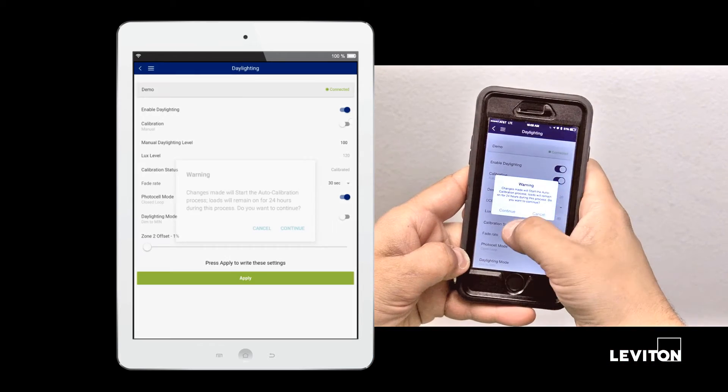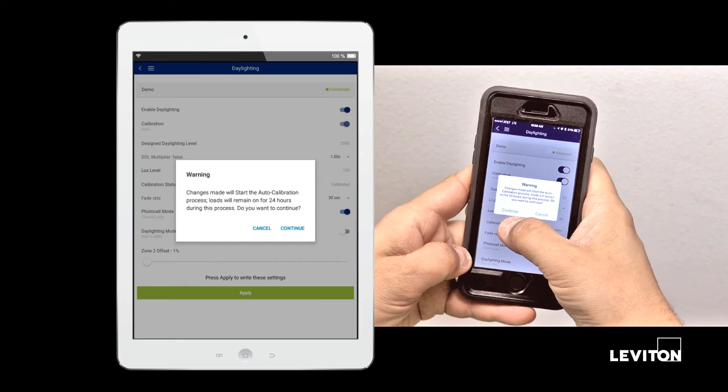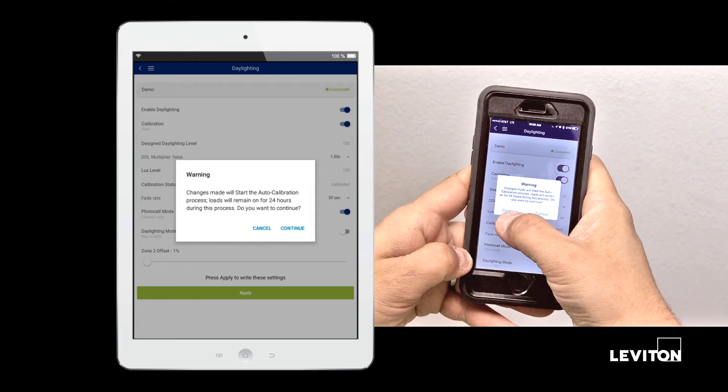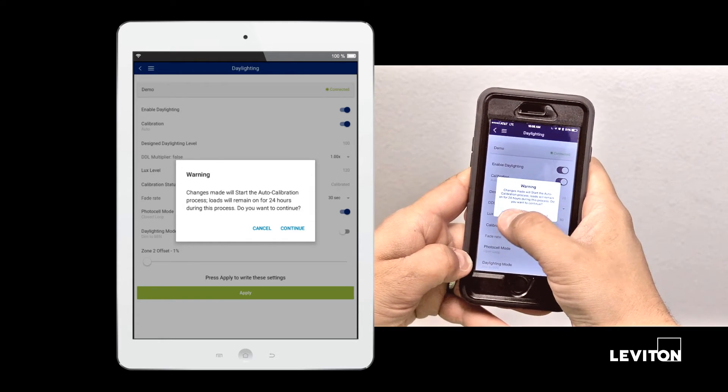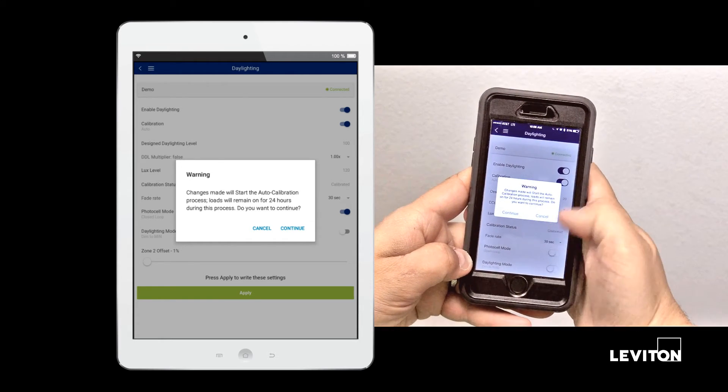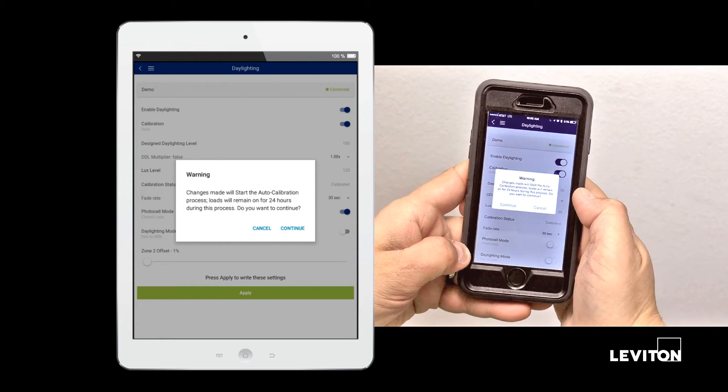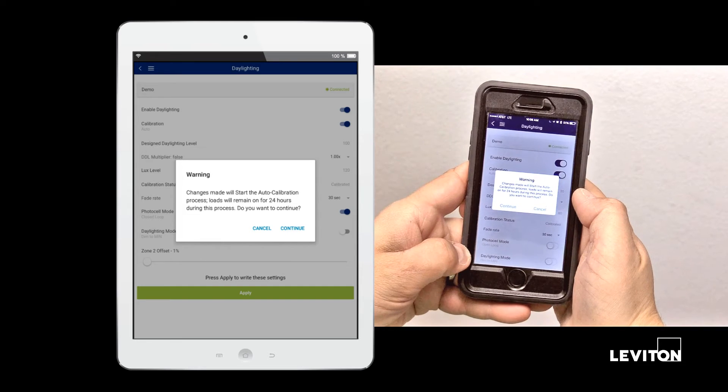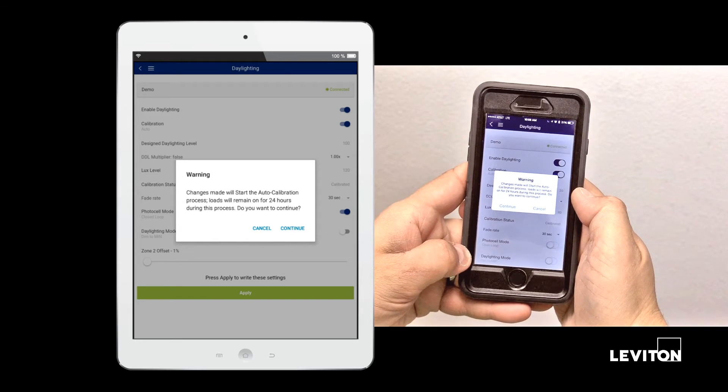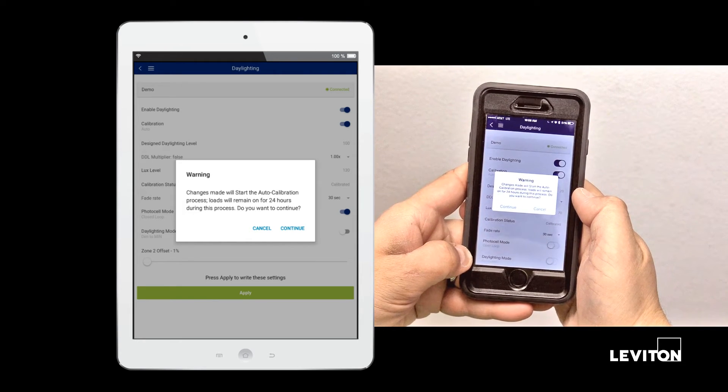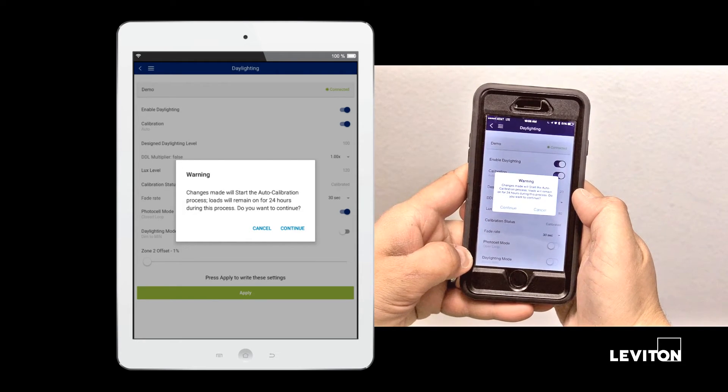To configure auto calibration mode, set your toggle to auto. You'll get a warning indicating that this will start the auto calibration process. Entering this mode will start a 24 hour calibration process.